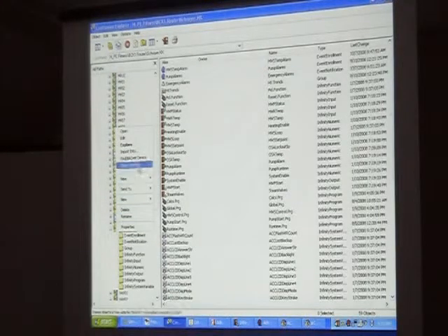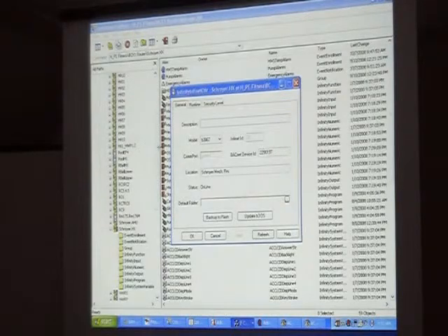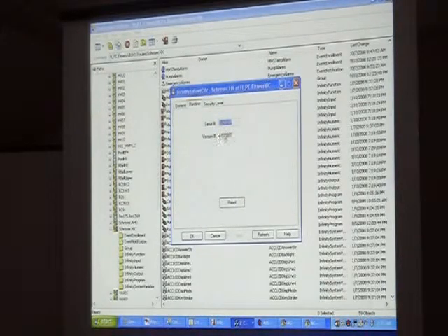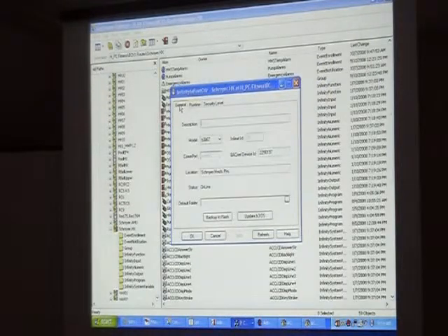If I right-click that controller itself and go to check the comm status, it says status is online, right? The BACnet device ID matches the serial number on the controller, and the serial number has to be the serial number right here. So if you guys are having other issues, communications-wise, your serial numbers have to match up. If somebody goes in and inadvertently changes this number, that controller's not going to communicate anymore. That's the way it addresses. It uses serial numbers to address. That's all stuff that we'll get into more later, too.